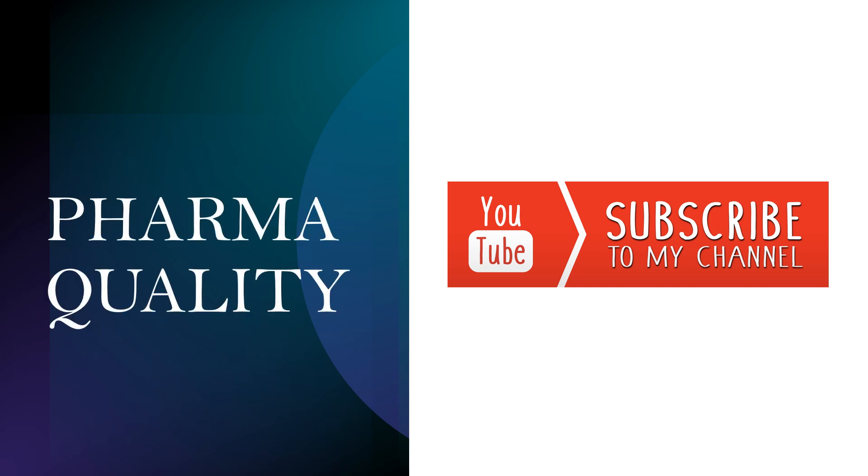My YouTube channel name is Pharma Quality, so please like, comment and subscribe. Now, first we will discuss the burette calibration. I am taking the example of a Metrohm Karl Fischer titrator. First, switch on the instrument from the power supply and from the instrument itself.